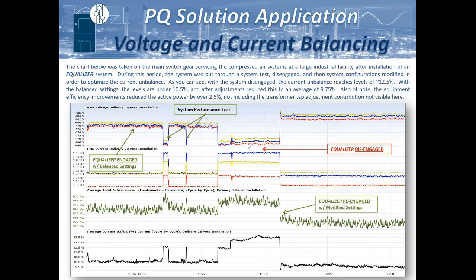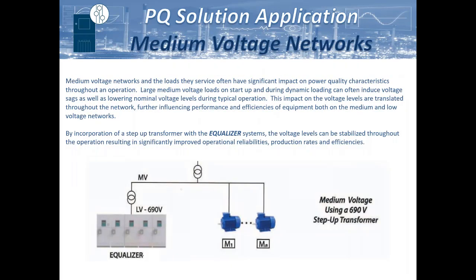And you can see that when we had the system disengaged, there was a significant amount of imbalance incurred. So I had them tweak some of the controller settings, and we actually raised the voltage even higher. But by improving the balance even further, we were able to get a better efficiency rating on their network. So, which is just another benefit. And we can also do these for medium voltage networks as well.